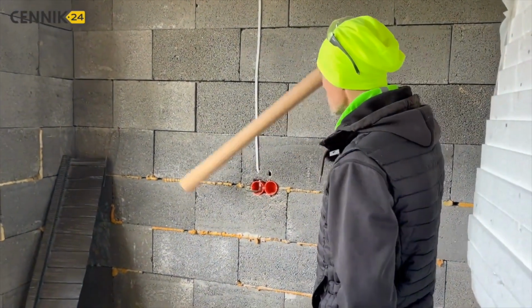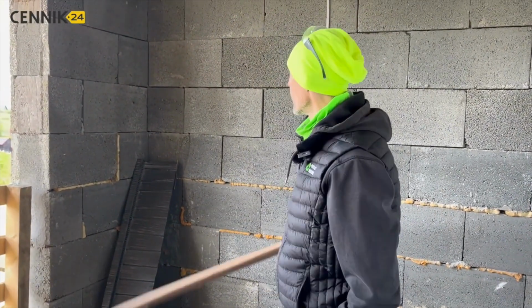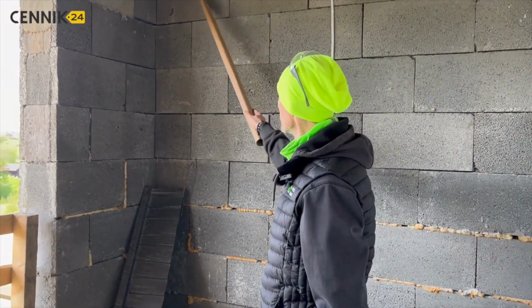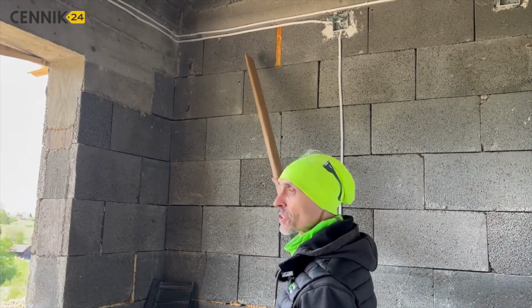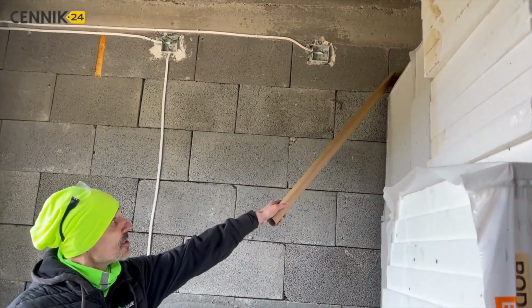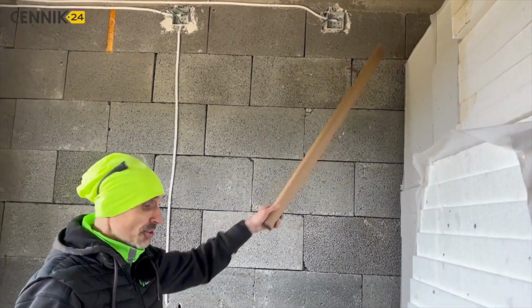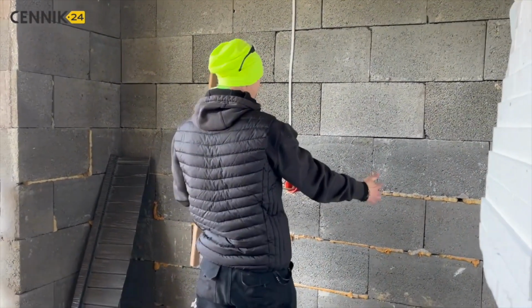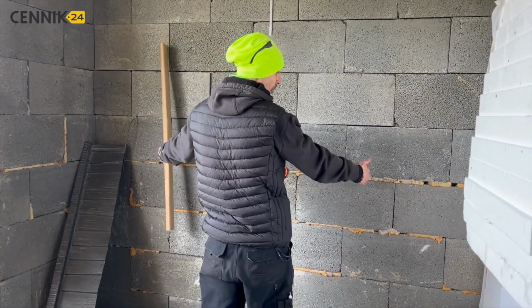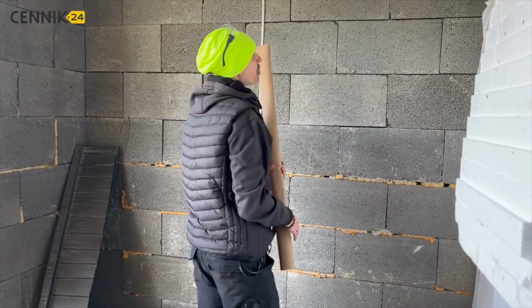We are in the garage, and on this wall, the heat recovery unit will be located. This is the north wall in terms of geographic directions, so somewhere around here on this wall, the intake grill is planned. Meanwhile, at a distance of at least 1.5 meters, the exhaust grill will be installed. This actually works out nicely, because the V-type heat recovery unit has the intake on the left side here, and the exhaust on the right side here, so it will be a very simple setup to connect the unit directly to these wall penetration points, meaning the intake and exhaust.